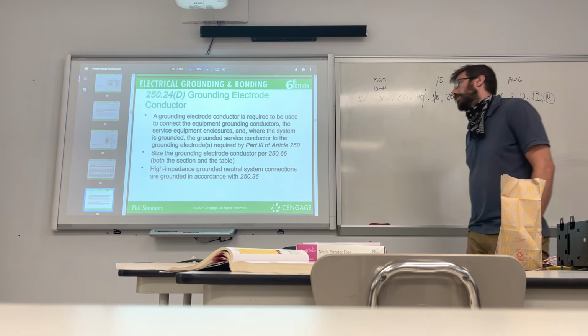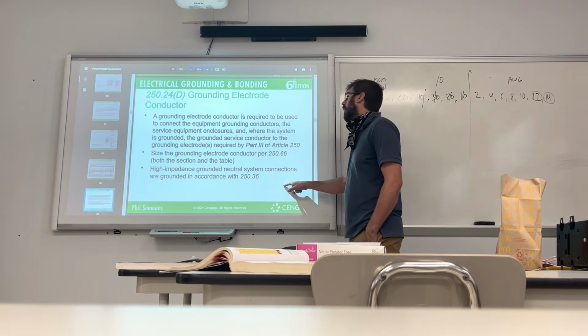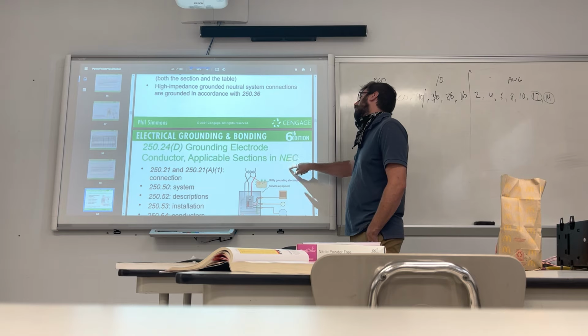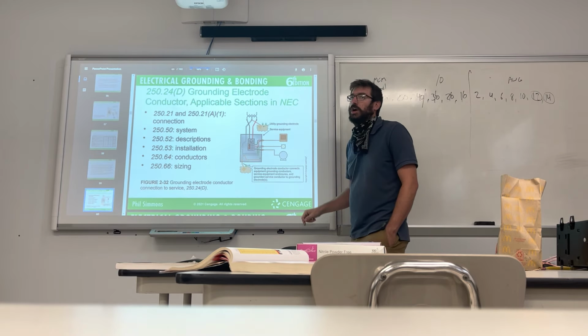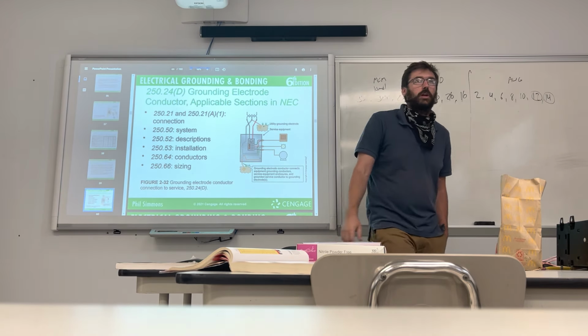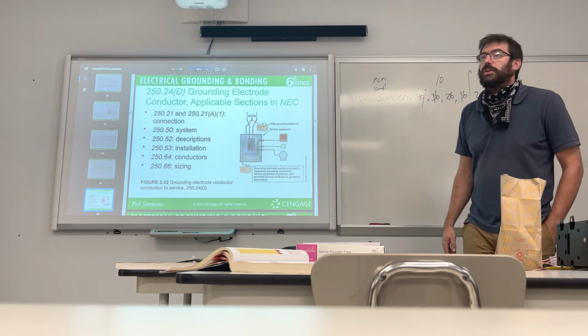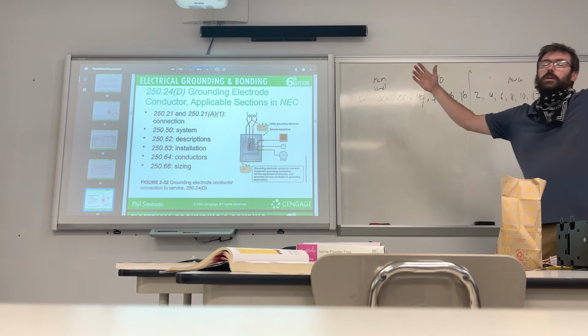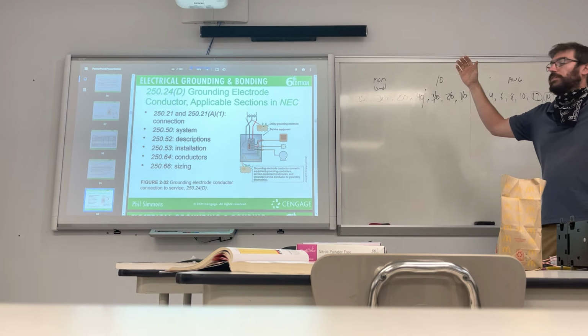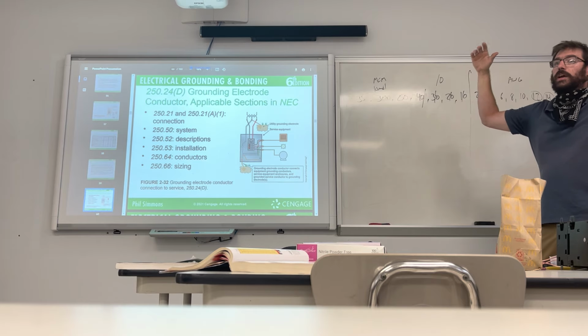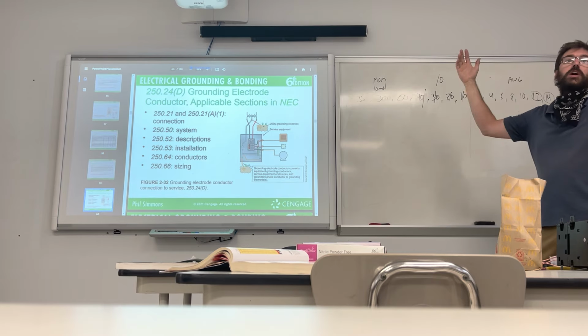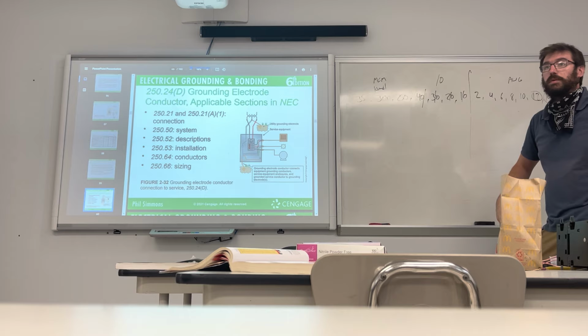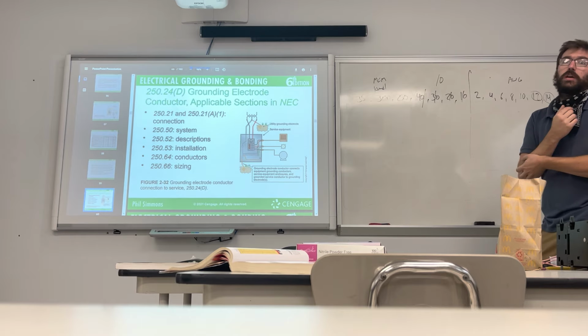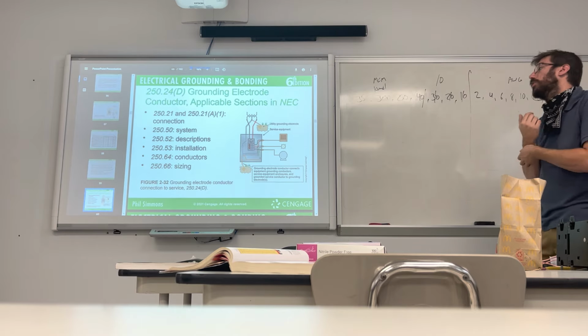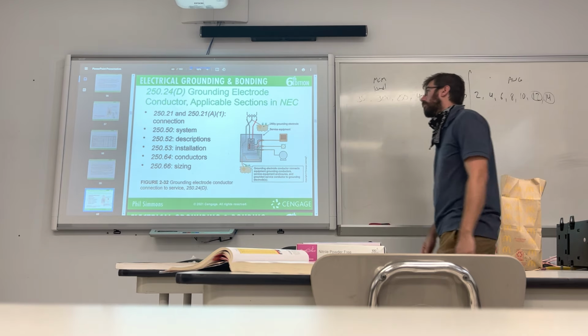Most ground rods are 8 to 10 feet long. And usually any bit of steel that's slammed into the ground 10 feet or longer can be considered a ground rod as well. So if you have a big, huge pole barn, I say pole barn affectionately, if it's a steel pole barn, it might be 40 feet tall. Well, those beams might be in the ground 10, 12 feet. If they're in 10 feet or more, they can be used as a grounding electrode.